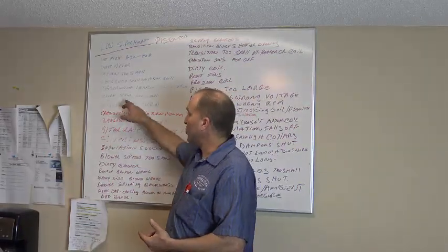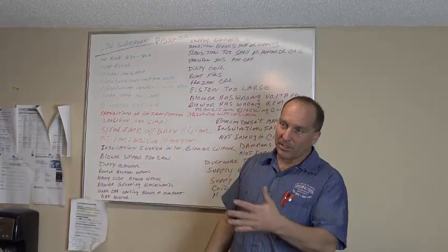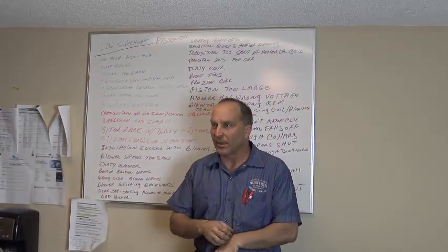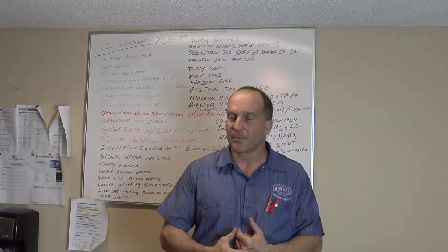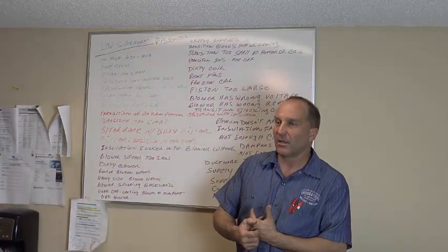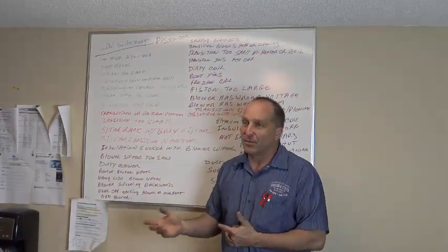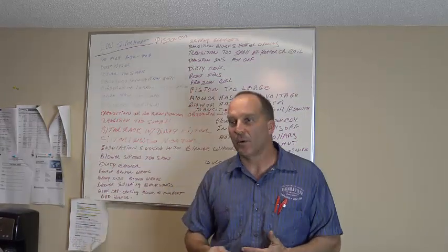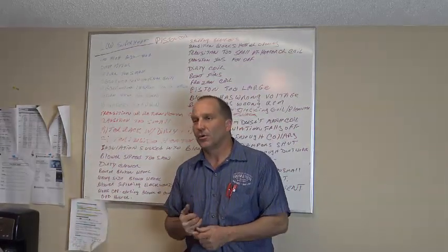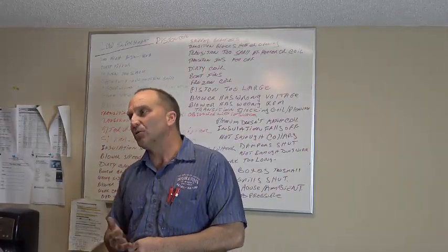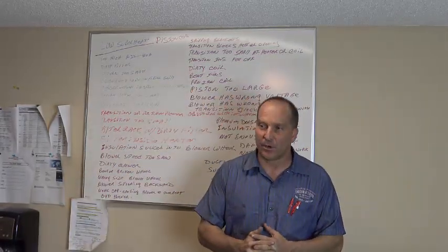So if your return chase is too small, you look at the filter grill on the wall, and the filter grill is a 24 by 24 with a 3-ton system, and that's fine. Because height times width times 2, 24 by 24 gives you 1152 CFMs of airflow for your return. Height times width times 2, write that down and remember that. That is your return grill size. Height times width times 2 gives you the CFMs for your return air.